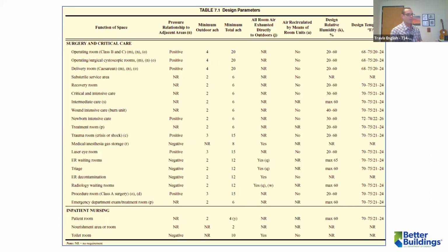If you're familiar with healthcare design, you probably know the ASHRAE Standard 170, which has a table full of air change rates: all exam rooms need 6 air changes, X-ray rooms need 6 air changes, etc. We didn't use this table on the project. If you use this table, it has a really big impact on HVAC energy. Similar to a lab, implementing high minimum ventilation standards really drives up your heating and cooling energy on an annual basis.